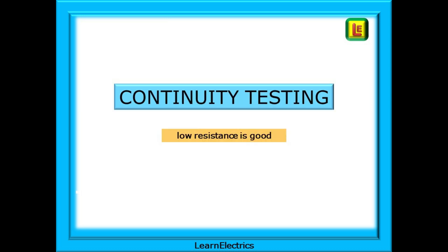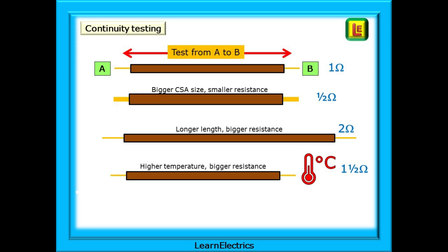We can look at continuity testing in a little more detail now. Remember that with this test the lower the resistance reading the better. If we set our test meter to low ohms and test the cables from A to B we might get a resistance reading of just one ohm. If we choose a bigger size conductor, say twice the cross sectional area, we find that the resistance value reduces as it is easier for current to flow. Thicker copper allows more current to flow and Ohm's law tells us this equates to a lower resistance - reduced to half an ohm.